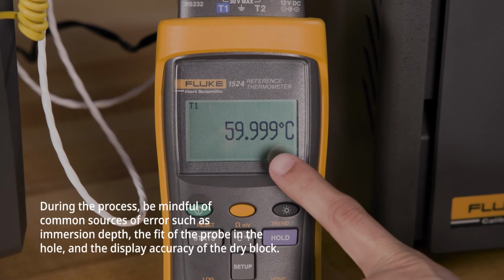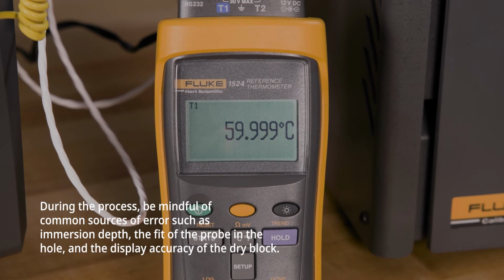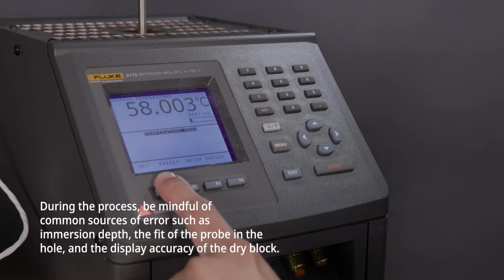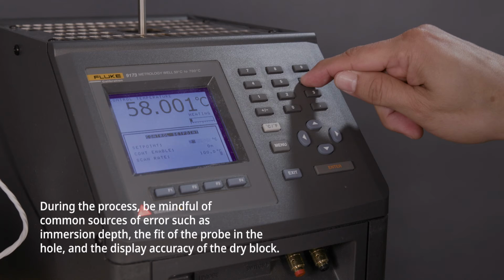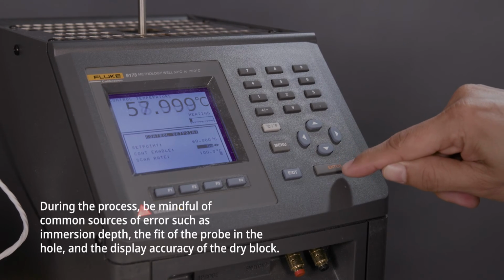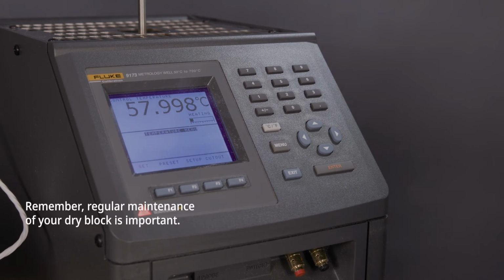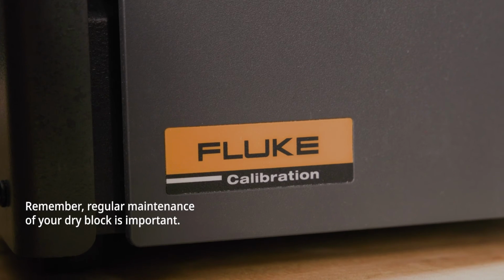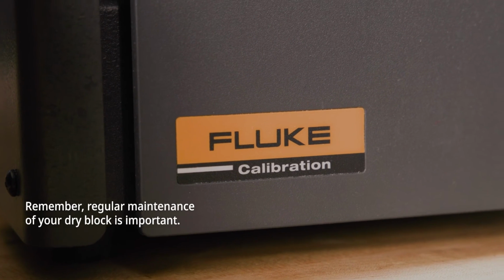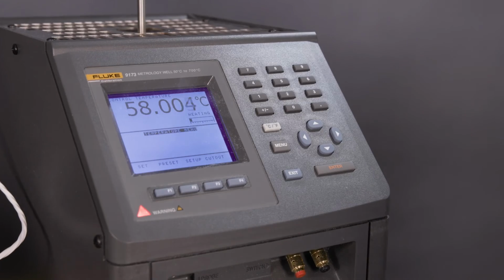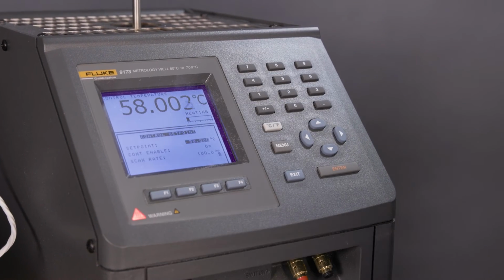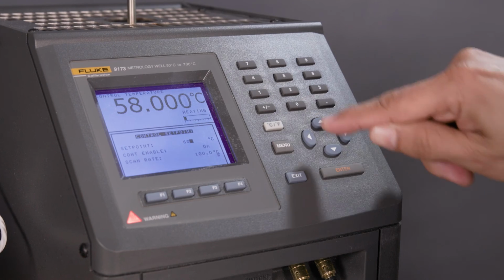During the process, be mindful of common sources of error, such as immersion depth, the fit of the probe in the hole, and the display accuracy of the dry block. Remember, regular maintenance of your dry block is important. Clean your inserts regularly and avoid using thermal grease or paste that can damage the block or inserts.